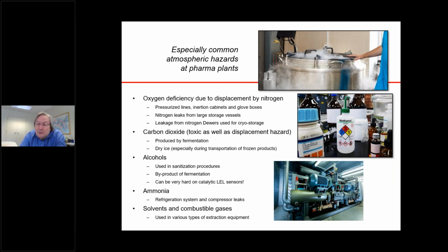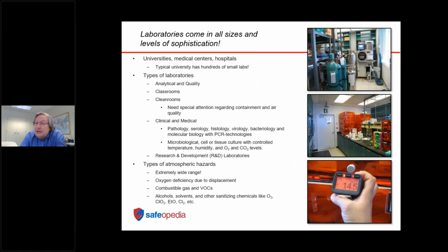So you have ammonia near the compressor, you have ammonia reservoirs on the ceiling, you have the potential for the release of ammonia that can get into vent lines and into plenums and all of these places. You probably should, if you've not already, think about adding ammonia monitoring. Sometimes the best approach is fixed, sometimes the best is portable. Often you need a combination of fixed and portable detection to be safe from all standpoints.